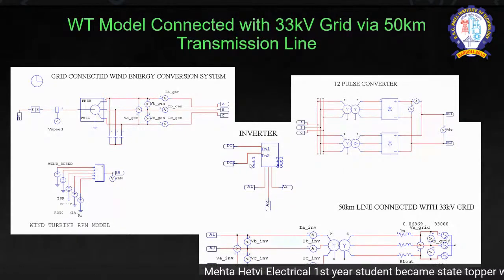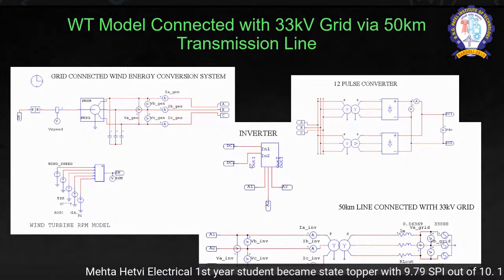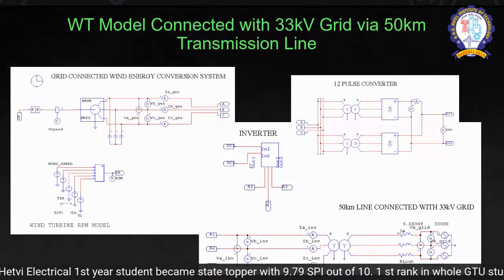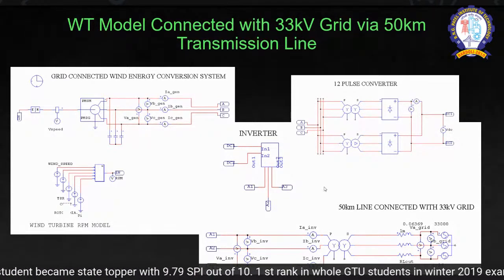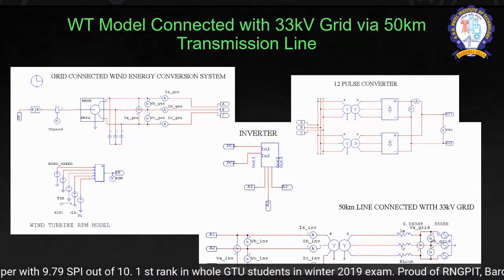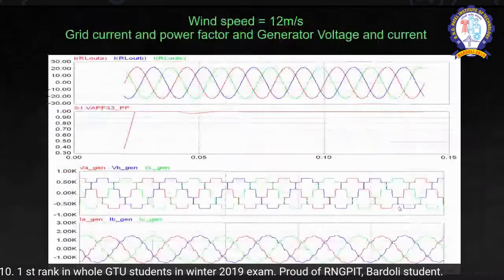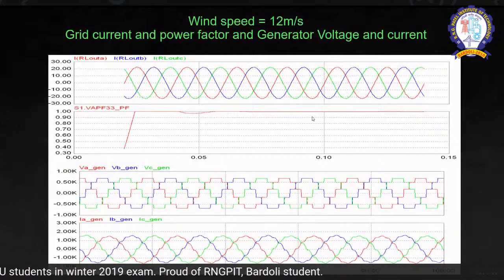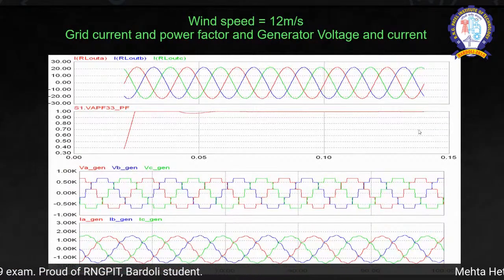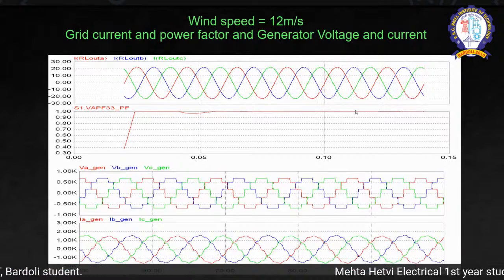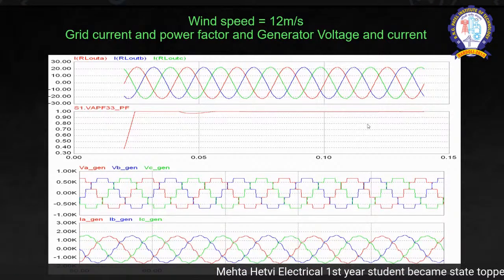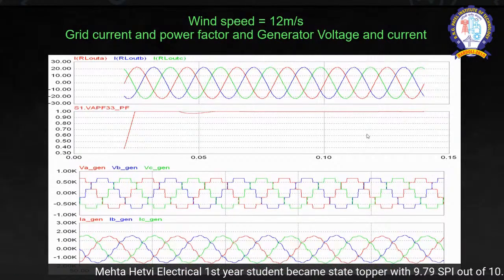They have offered me an industrial platform to perform this task and some hardware test measurement. This inverter is connected with the grid via a transformer. So this is our grid current. This is our grid power factor. As I initially mentioned, this grid power factor is usually nearly equal to 1 during healthy condition.